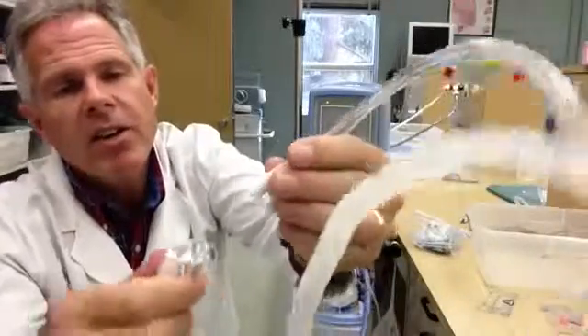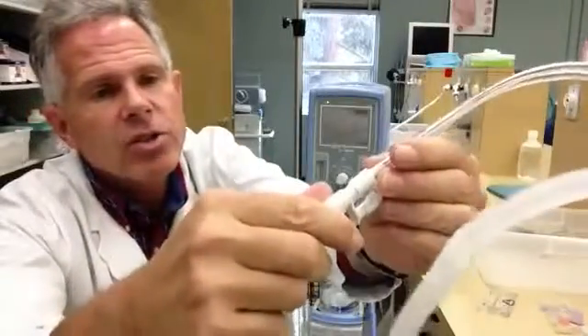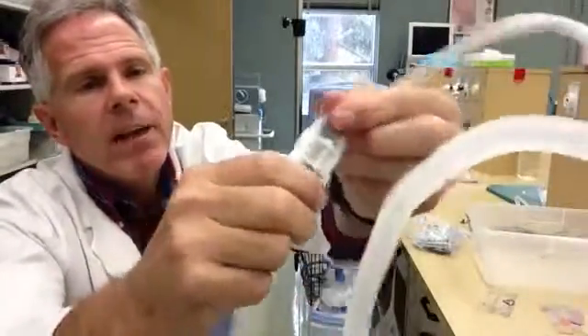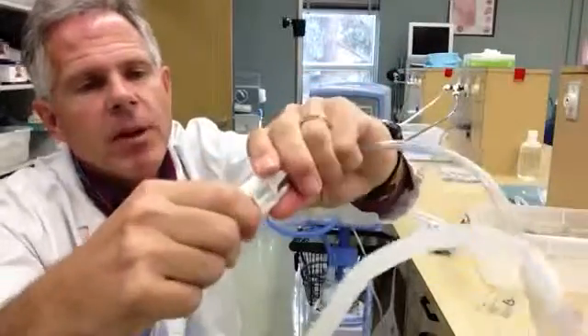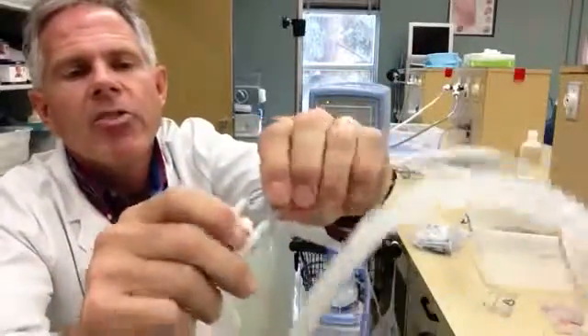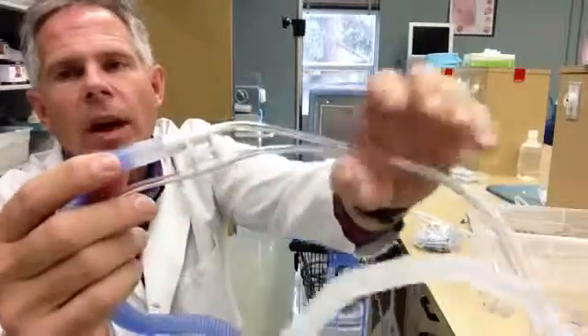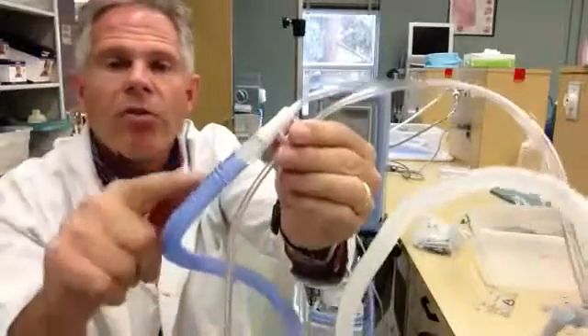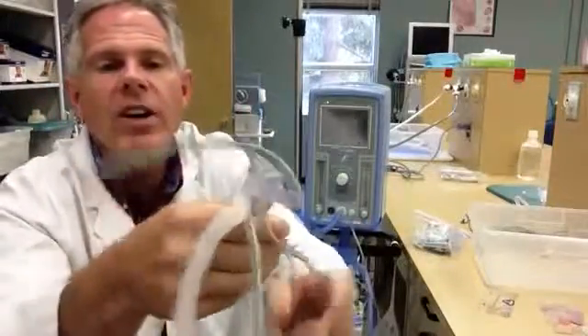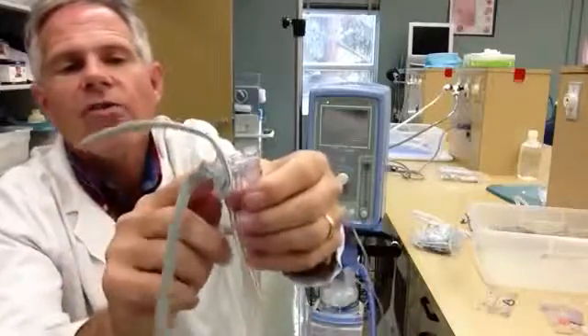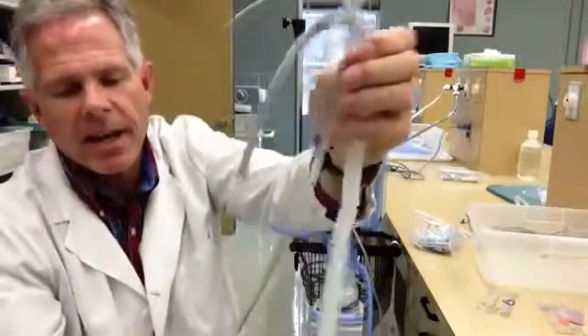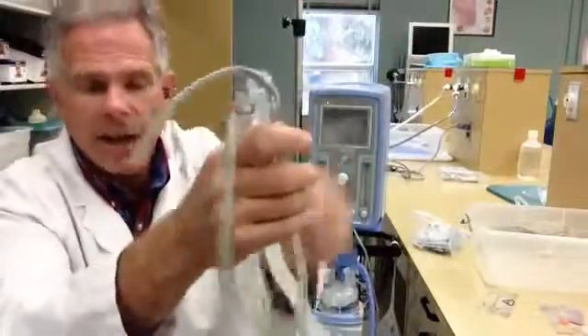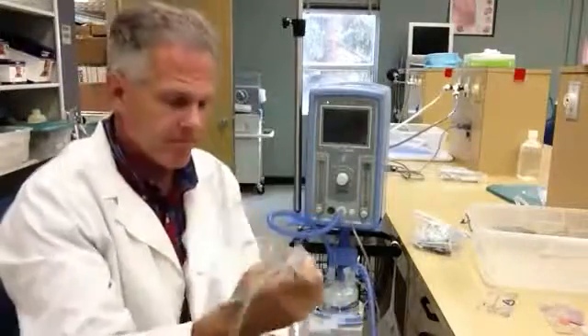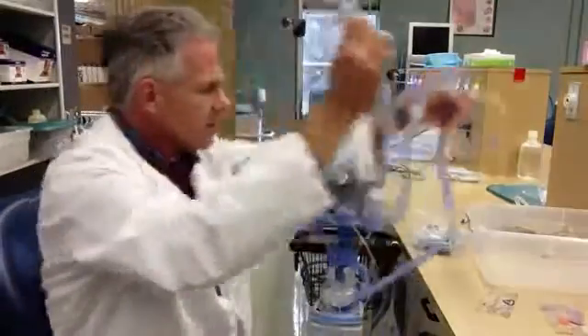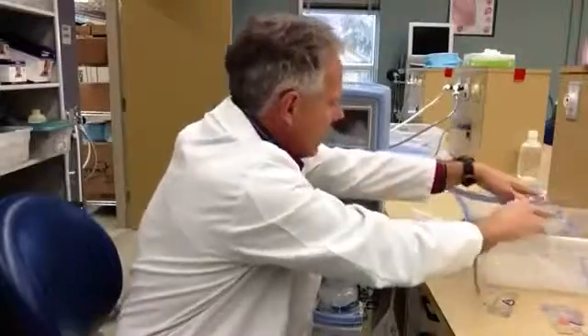And this part here hooks up directly to my circuit just here, and with a nice firm click, there we go, it just hooks up right onto there. Okay? So the gas flow comes from the ventilator up through this narrow line, right to this little flip-flop device here, and back against our pressure manometering line, back to the ventilator. So I'm going to just set this off to the side right now, keeping that clean.